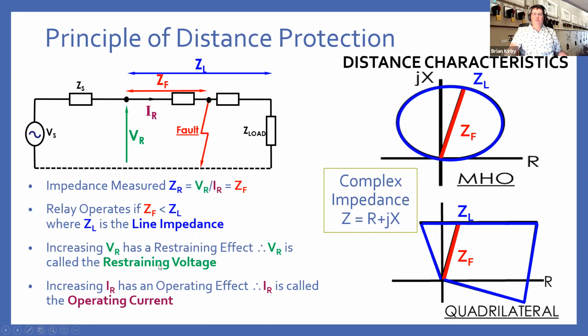We have a voltage, which is restrained. So as your voltage increases, the likelihood of you being inside your fault characteristic reduces. So that's said to restrain your protection. However, as your current increases, then your impedance will fall. Therefore, the likelihood of you being inside your characteristic increases, and that's called your operating current. But as I mentioned, with our AC networks, we have complex quantities. We typically have a 70-degree characteristic angle, so we have to do this calculation in the complex plane with active and reactive power.